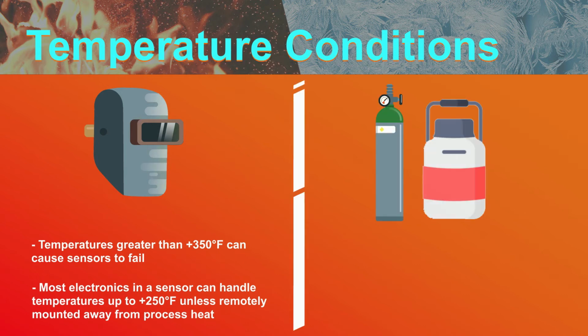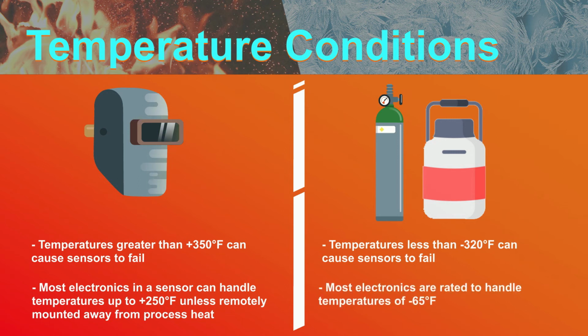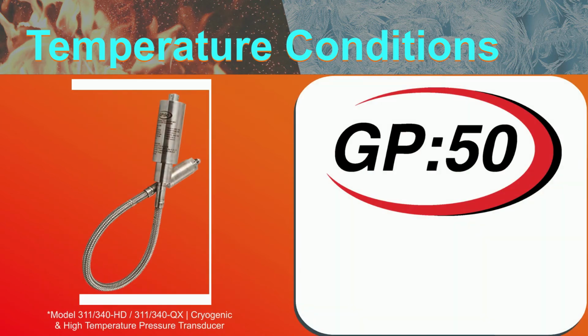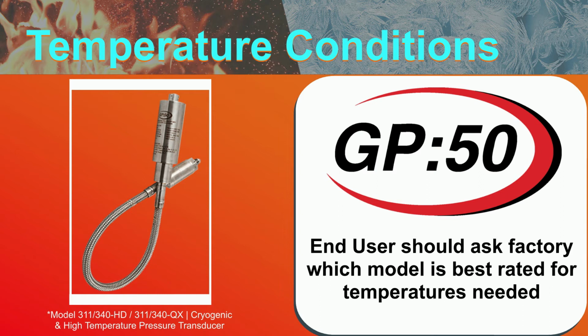Cryogenic temperatures less than negative 300 degrees Fahrenheit can also cause a sensor to fail, and most electronics are rated to minus 65 degrees Fahrenheit. If you have an application that runs to extreme temperatures, it is always best to ask the factory which model is best rated for these temperatures.